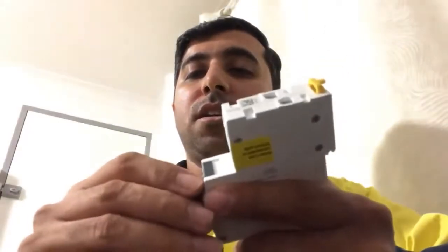The next one is the safety switch. This one that I have in my hand is actually a safety switch slash circuit breaker. The appearance somehow looks the same as the circuit breaker. As you see, the difference is there is a small switch like this one, on which the letter T has been written. T stands for test. That means it provides all the protective advantages of this one plus the safety switch. What is called a safety switch? The correct name for that is actually residual current devices.